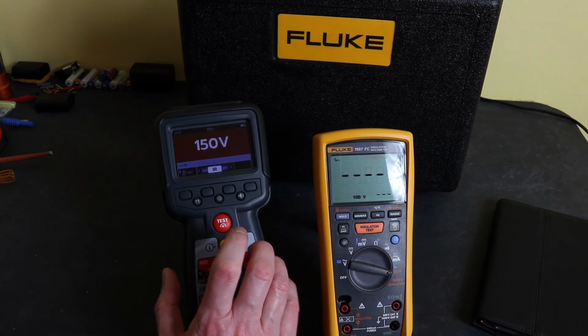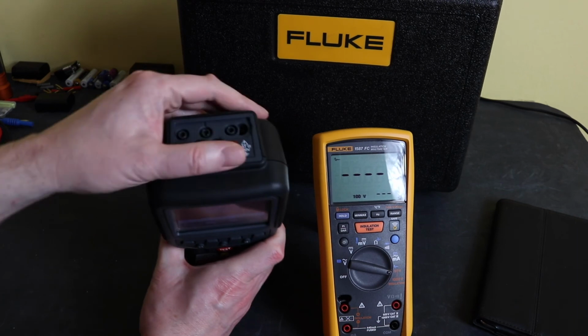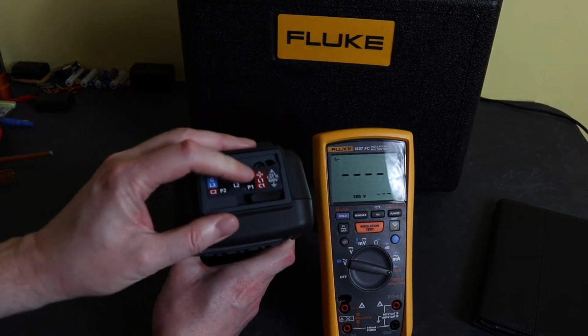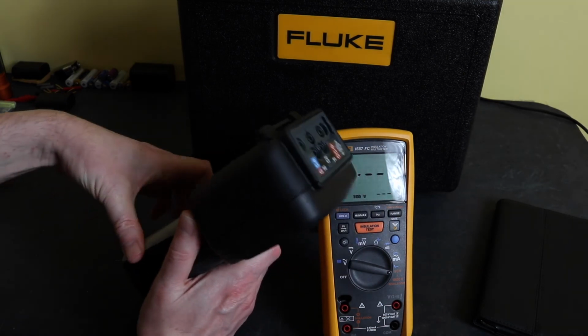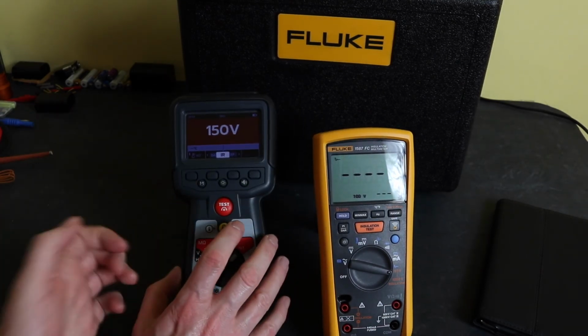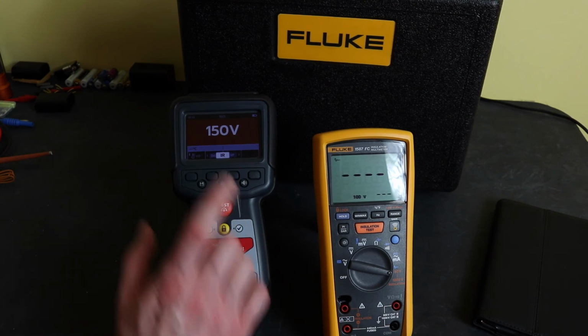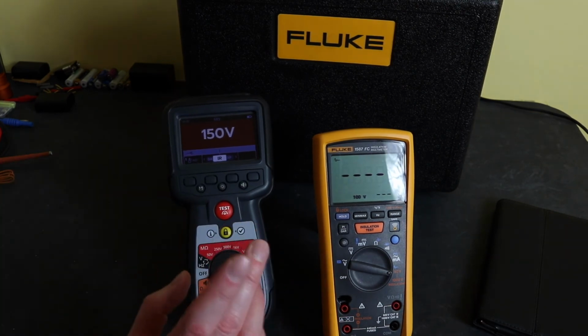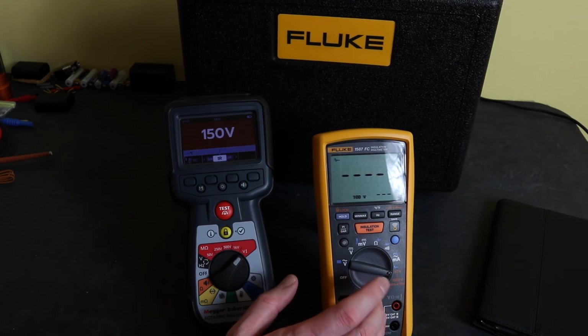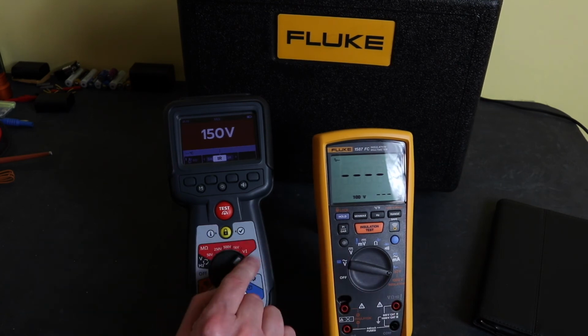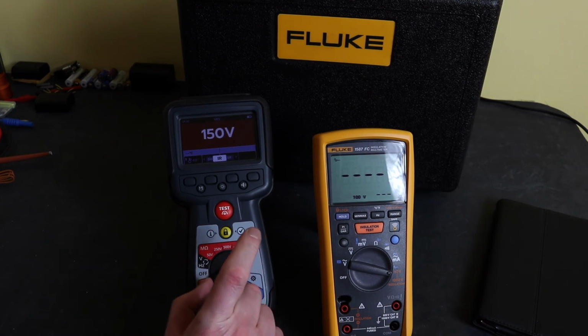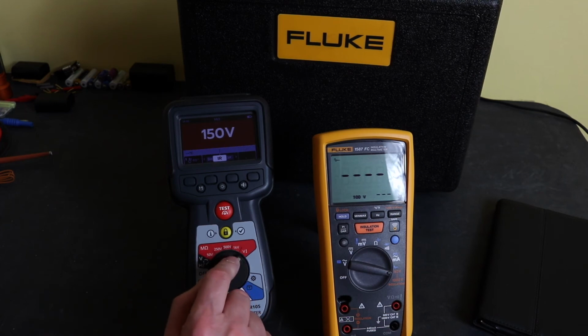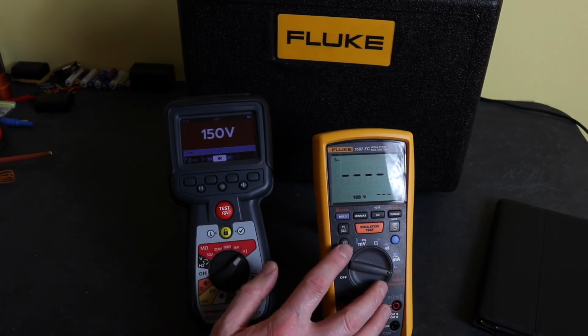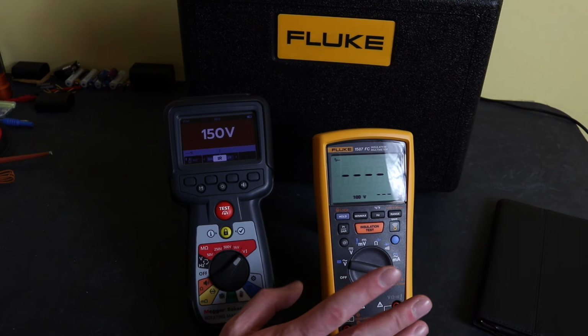In contrast, the MTR105 has a USB port at the top here that you plug a USB stick into, and all the testing that you do is done to internal memory, and then you transfer that internal memory onto the USB stick. Whilst this instrument can record a whole polarization index curve, this can't. You just get the 1 minute, 10 minute values along with the index ratio. And if you want any extra data, you have to record that manually and then enter it manually into a computer. Whereas with the 1587, that's all done for you electronically.